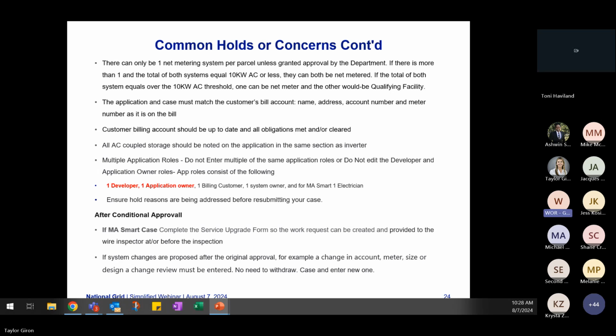Some more common holds here. Do not forget that there can only be one net metering system per parcel unless granted approval by the DPU, Department of Public Utilities. If there is more than one system on the parcel and both systems equal 10 kW or less, they can both be net metered. However, if the total size of both systems equals over 10 kW, only one of them is allowed to be net metered and the other must be a qualifying facility.